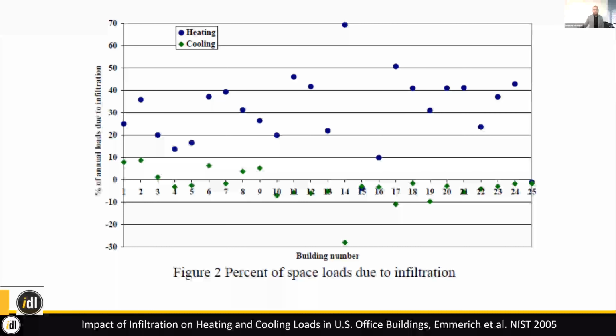The infiltration, the drafts coming into the building, were driving 30% or more of the heating load. So if you're trying to reduce gas usage or electricity consumption in the wintertime, particularly in northern Idaho at the Vista, they have a winter peak in terms of their utilities, so they're really focused on this. You really want your building to be tighter rather than having essentially windows that are just open in random places, pulling in that winter air.